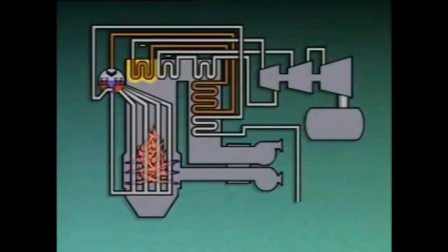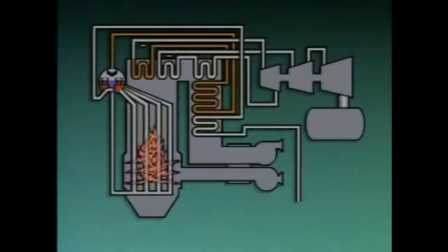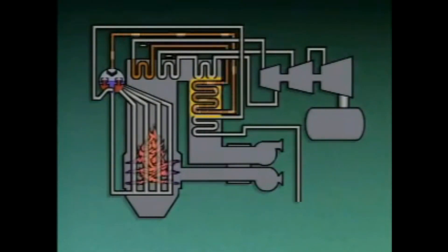A radiant superheater is in a direct line of sight with the flames in the boiler furnace, and it receives most of its heat by radiation from the flames. A superheater may also be classified as a primary superheater or secondary superheater. A primary superheater is the superheater that the steam passes through first. It is usually a convection superheater, and it is generally in a cooler location than the secondary superheater.